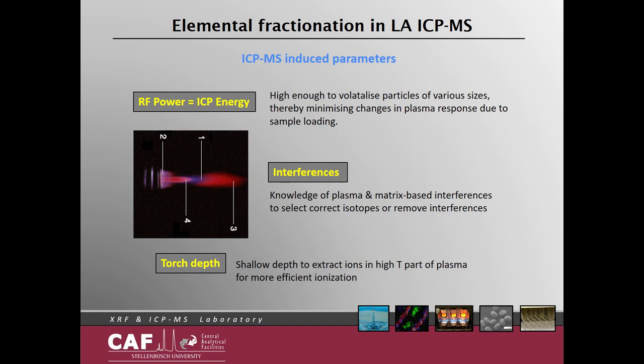Looking at ICP-MS induced parameters that can lead to elemental fractionation: firstly, the RF power should be high enough to volatilize particles of various sizes, thereby minimizing changes in plasma response due to sample loading. Secondly, interferences on analytes can cause incorrect results — one needs to have knowledge of plasma and matrix-based interferences to select the correct isotopes or remove interferences. Thirdly, shallow torch depth is best for optimal ionization of all elements and particle sizes in the sample.